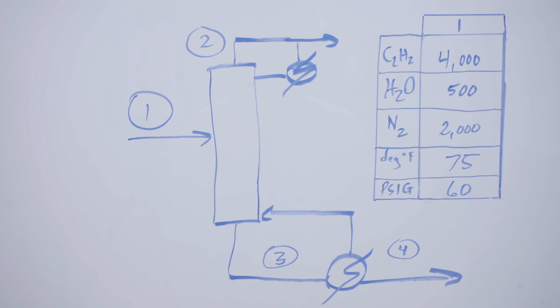expecting. Sometimes in these, it's good to put what's the max you're expecting, or if you have multiple modes within the same equipment, you may want to do a different column for modes. You may want to do a whole other process flow diagram for a different mode that you have. Let's say you're in a regeneration mode for processes that regen catalysts, or if you're running in a single pass-through mode or 2 concurrent lines running, if that changes the streams or changes any of your conditions.